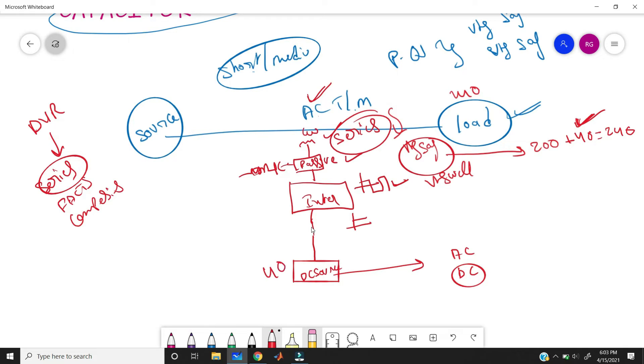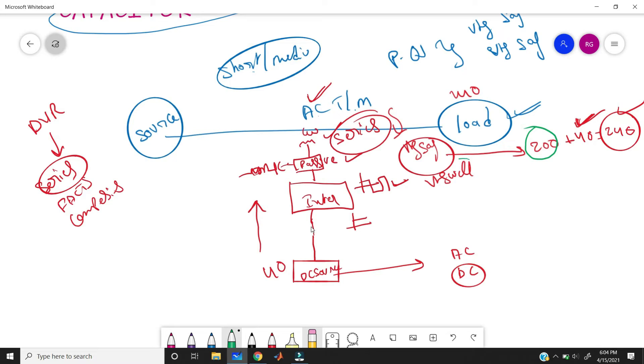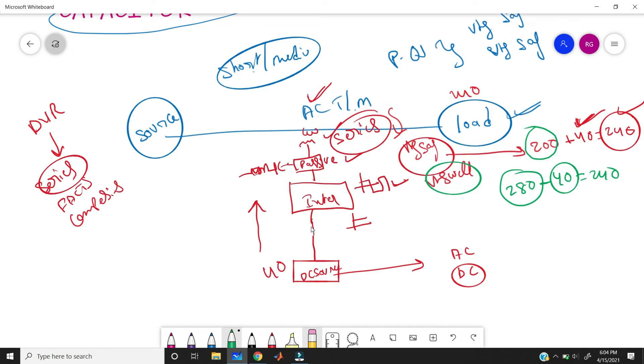Whenever we are getting 200 volts at the load, we inject 40 volts from the 40V DC source to eliminate the voltage sag and restore the rated voltage. But what about the voltage swell condition? For example, if we are getting 280 volts — 40 volts more than the required 240 volts — we have an excess of 40 volts. To handle both sag and swell, instead of a plain DC source we use an ultra capacitor, which can both store and release energy.